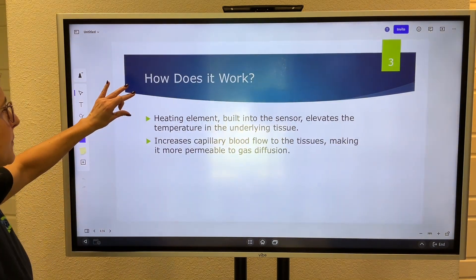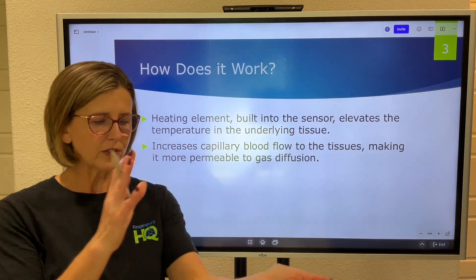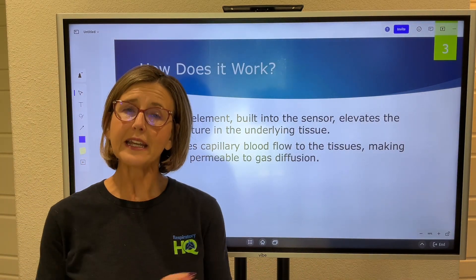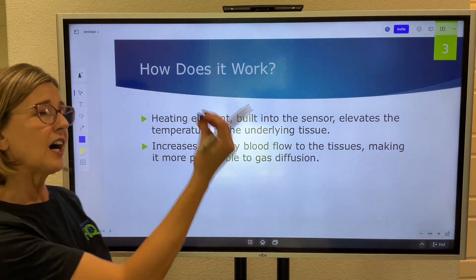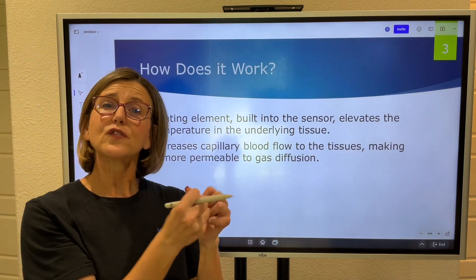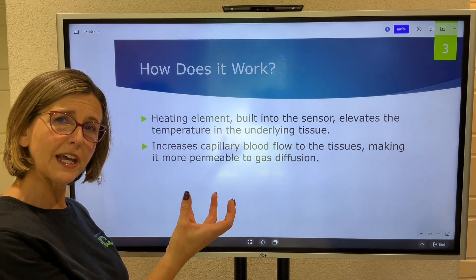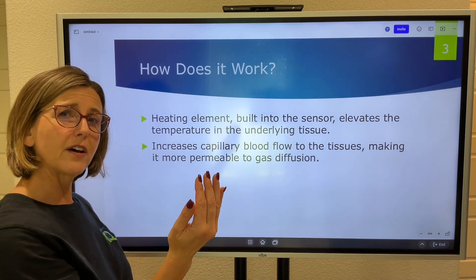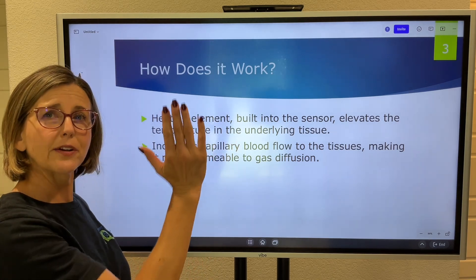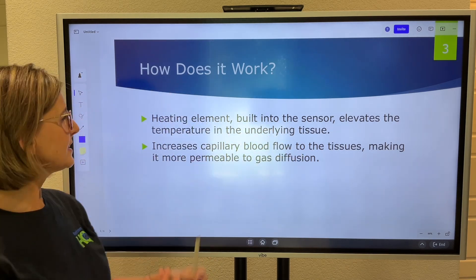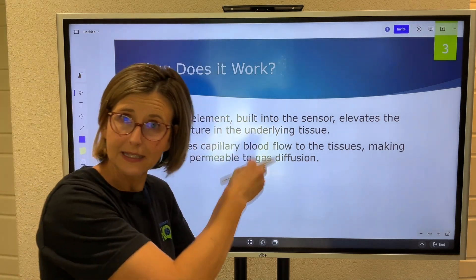How does it work? In that sensor there is a heating element. When you place it on the baby's skin, it heats up the tissue so that vasodilation occurs in the underlying area. When that vasodilation happens, oxygen and CO2 diffuse out of the capillary beds of the tissue into the sensor more readily. So this sensor has to be heated.